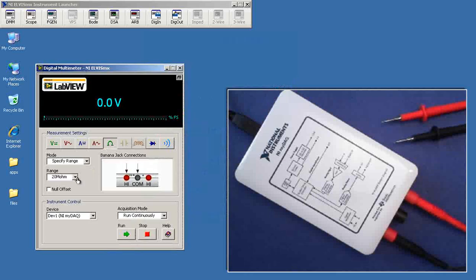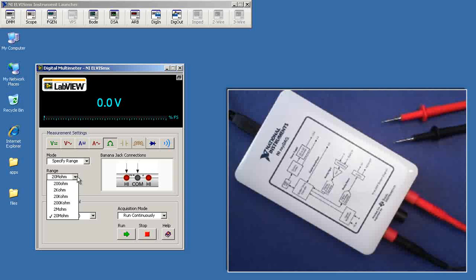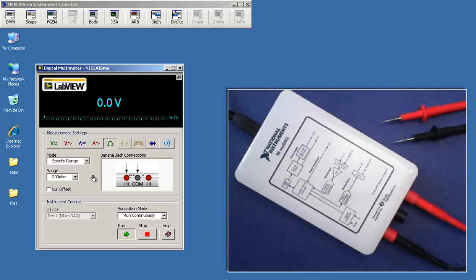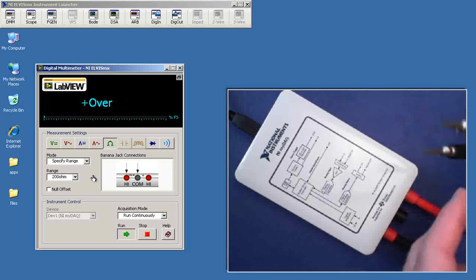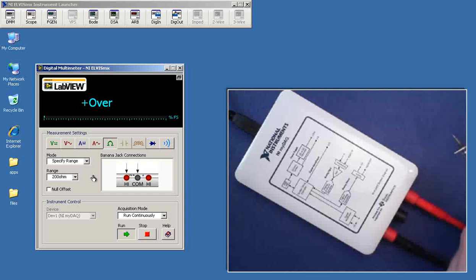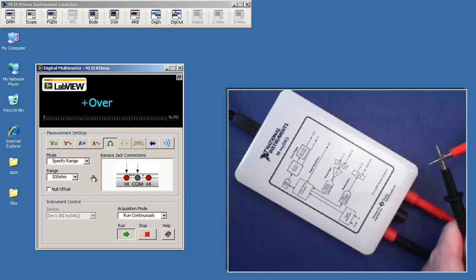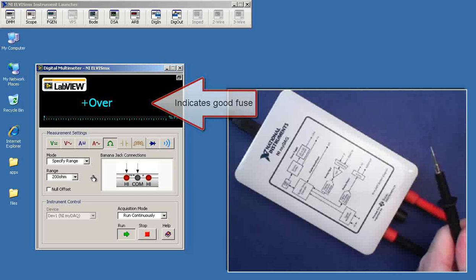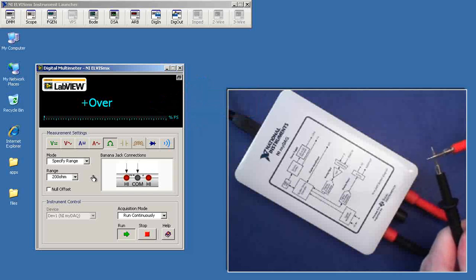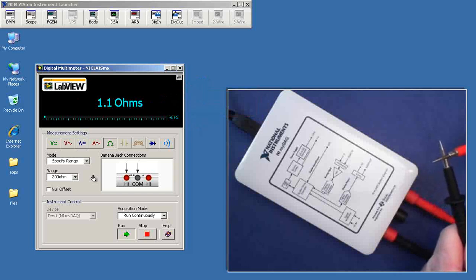Now, I expect that resistance to be quite low. I will use the 200 ohm range and then touch the DMM probes together in order to complete the connection between the ohmmeter and the ammeter. And I see resistance right around 1 ohm, and that indicates that we have a good fuse.